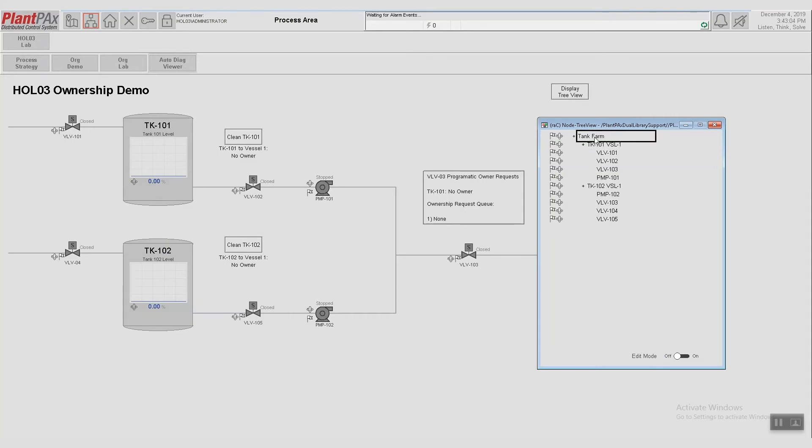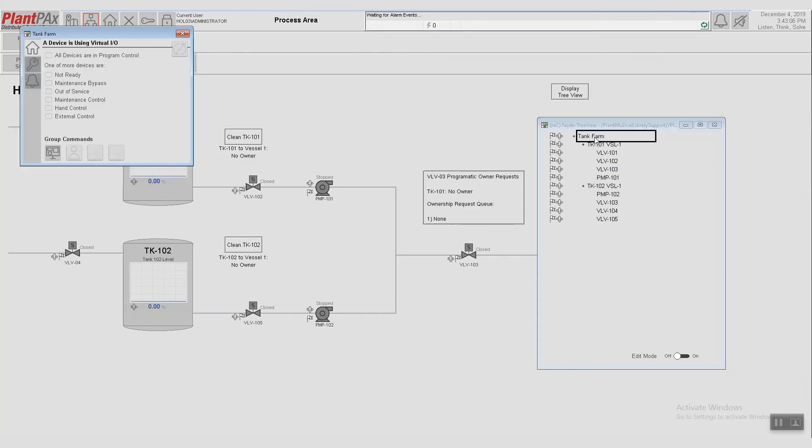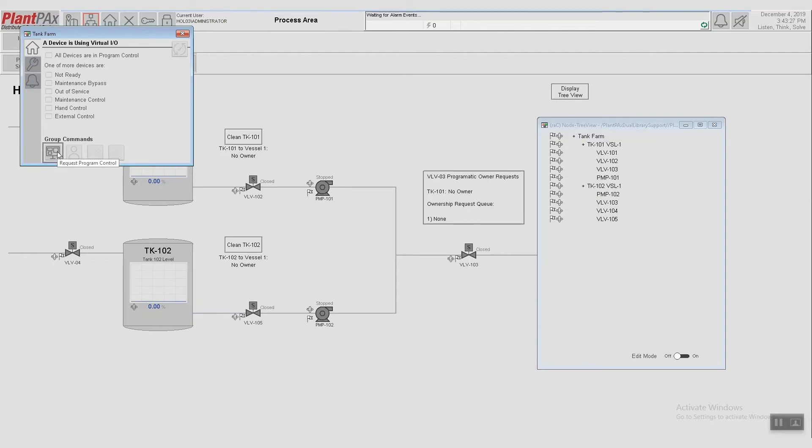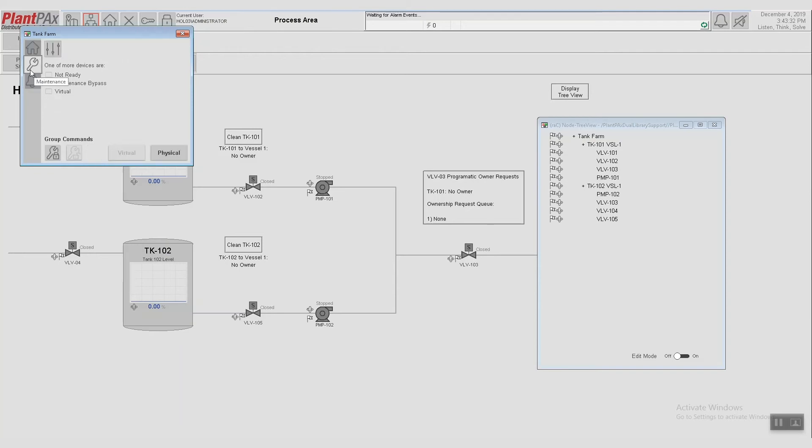So closing this, we can click on one of the nodes again. And now it pops up with a different faceplate. So this faceplate is really similar to what you see as a faceplate with current process objects. So we can see if the devices are in program control. We can see different information about those children, if something's not ready or if it's out of service. We also have the ability to put everything into program mode or operator mode or external.